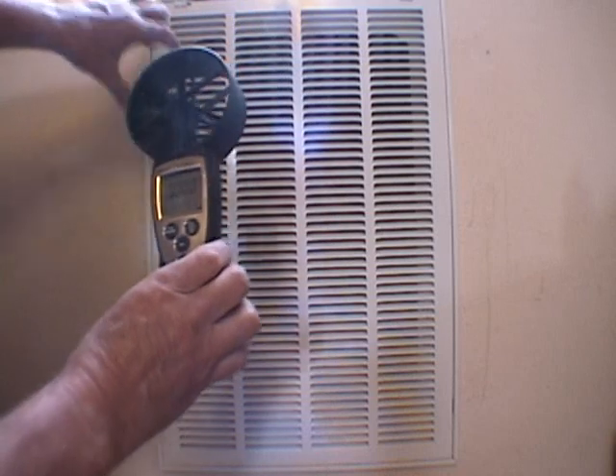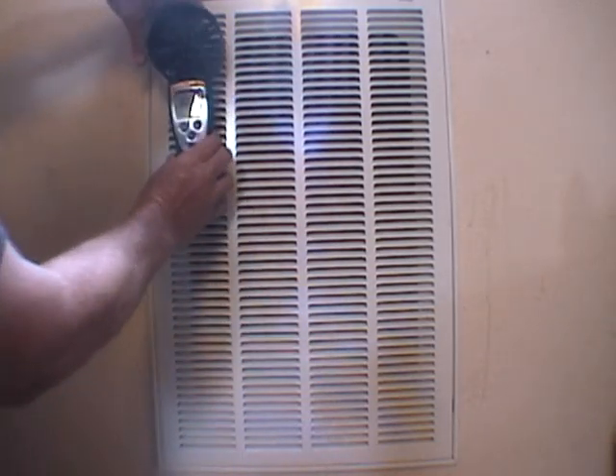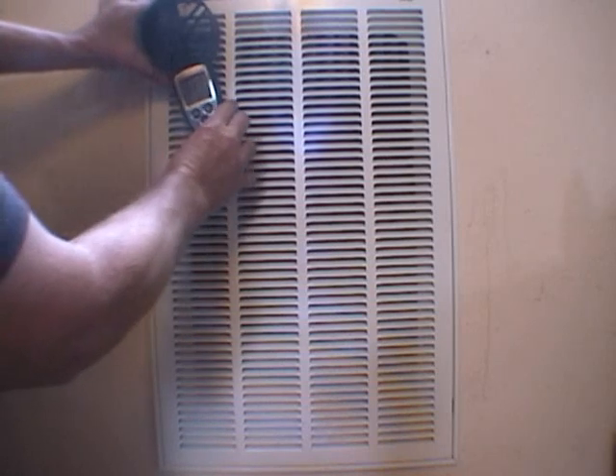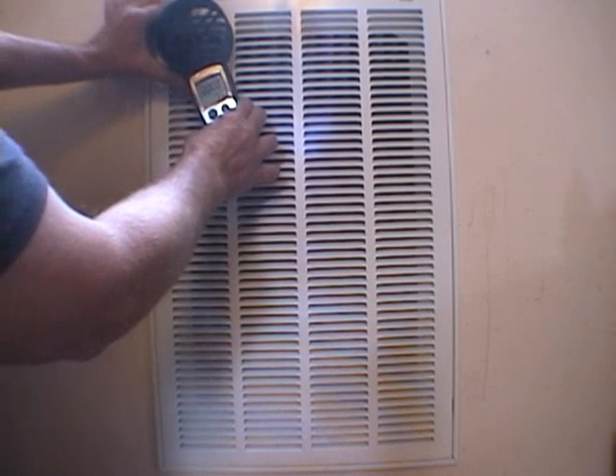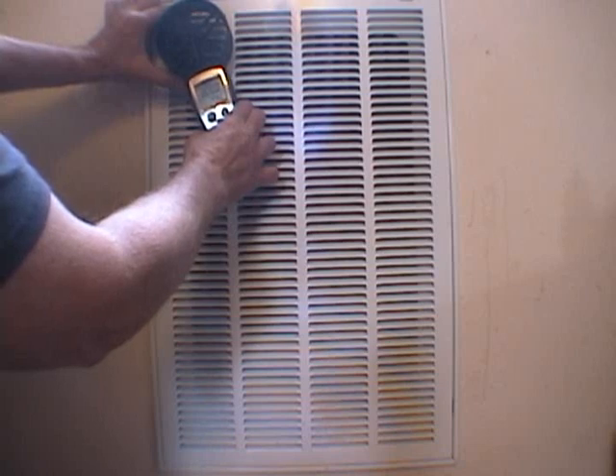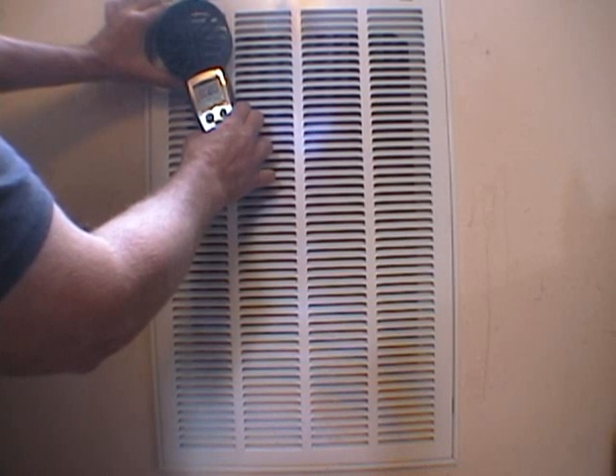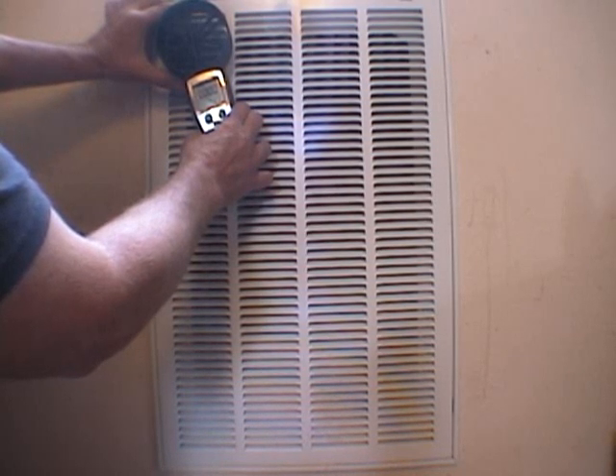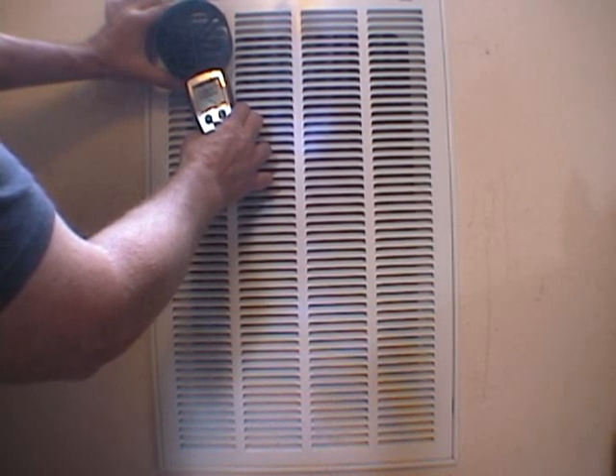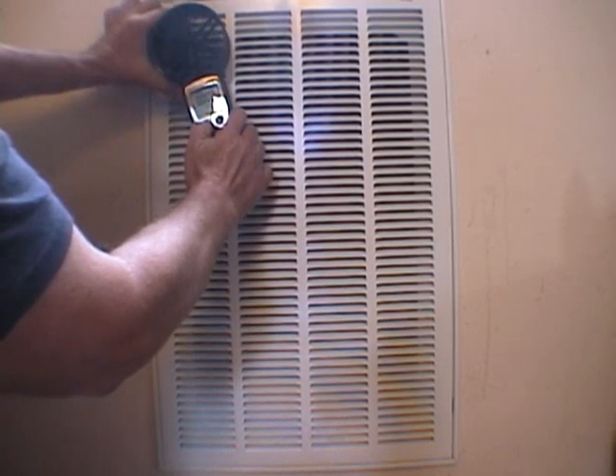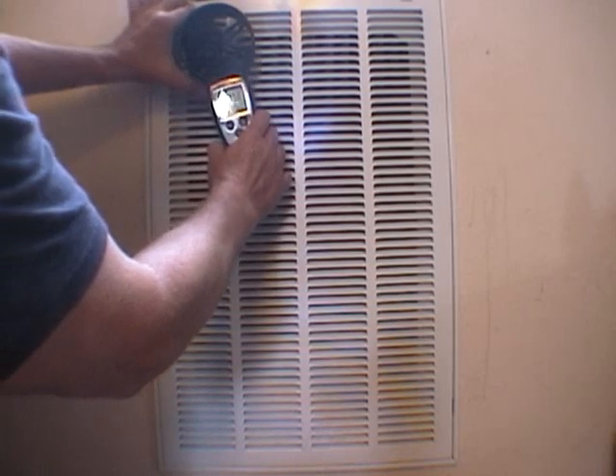I'm going to start in this corner, use my fingers for a one inch offset. Technique is everything here. I'm going to wait until it gets up to full velocity feet per minute, so we're up to about 230, 240, so we're there. I'm going to start my timer and start traversing this grill.